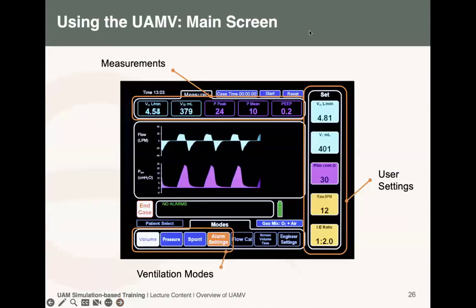Yes, you are very right. On the UAMV, there are set parameters which are in this column, but there are also measured ones which are in this row. That's why, as you have said, minute ventilation is important, because if you are not careful, you might either hyperventilate or hypoventilate a patient while he's on the vent. You can also monitor the tidal volume, peak pressure, mean pressure, but also the PEEP.